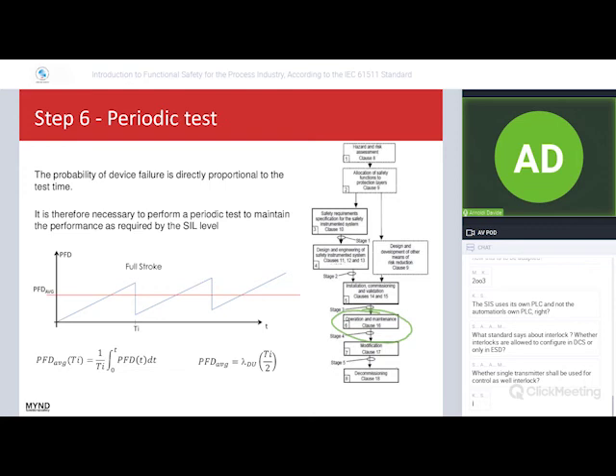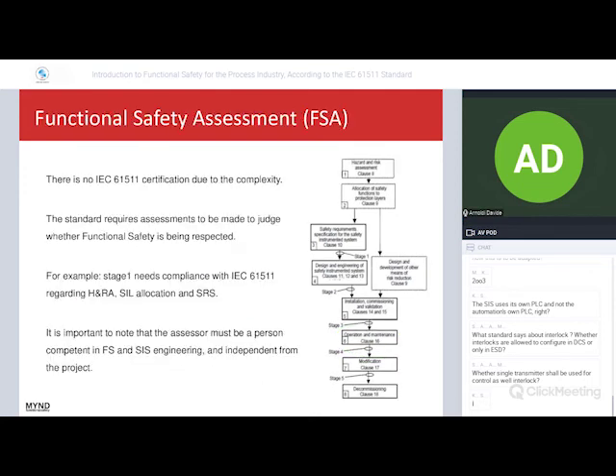You need to make some test of function from the sensor to the final elements. For example, proof test of the valve means to close completely the valve and to reopen the valve. This is the test in order to establish that the performance of the valve still remains for this safety instrument function. You need to prepare a procedure for that. You need to use the safety manual.